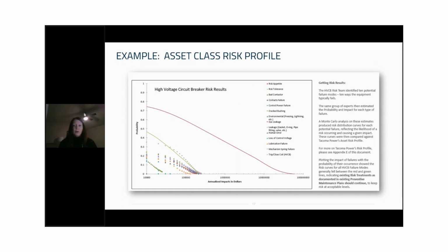Next, we show a summary of our risk profile for the high voltage circuit breaker asset class as a whole. The backdrop here is the standard risk profile map we use across all asset classes. It was developed in conjunction with our senior leadership team to identify our risk appetite and tolerance, and what it indicates is that any risk falling above the red line is unacceptable and needs to be immediately addressed. Any risk falling below the green line is something we're willing to absorb. So we may actually be spending there in an area where it would be better to do less mitigation. Anything falling between the red and green lines is something we're getting just right. Our maintenance and capital replacement processes are working to keep the risk at an acceptable level.